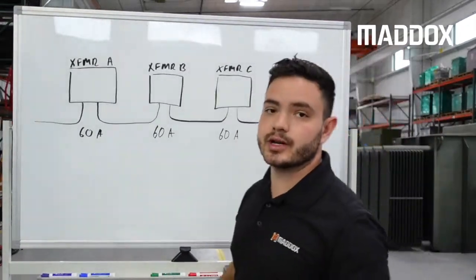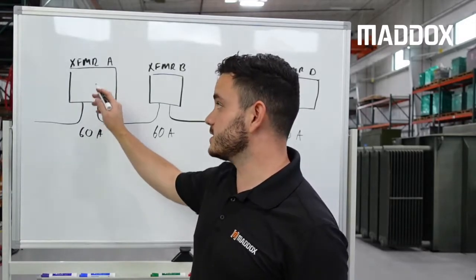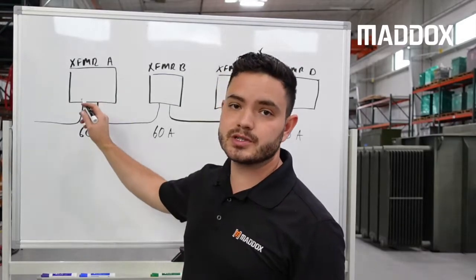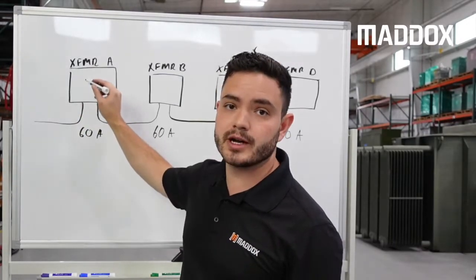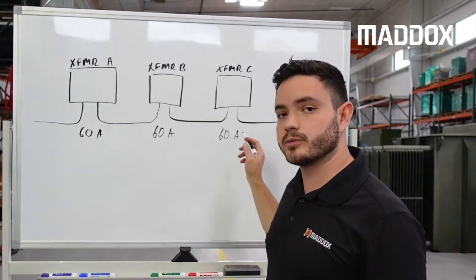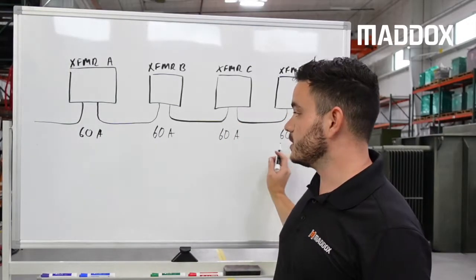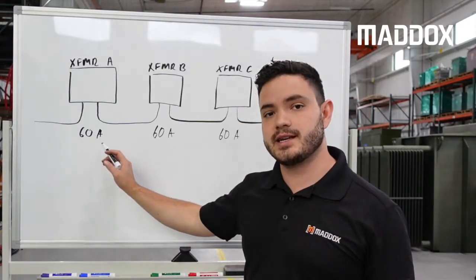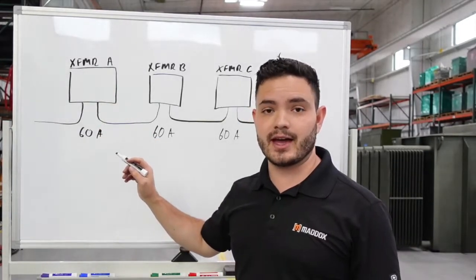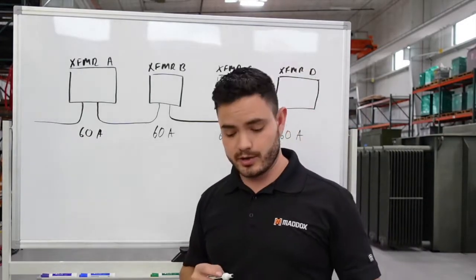Let's say transformer A has been calculated to be good for 60 amps on the primary bushings. That's great, but the bushings on the first transformer in the loop have to support the amperage of all the transformers downstream of it. In this example there are four transformers. If each is worth 60 amps at the primary, the first transformer will need 600 amp dead breaks because that's 240 amps — above the 200 amp load break bushing rating.